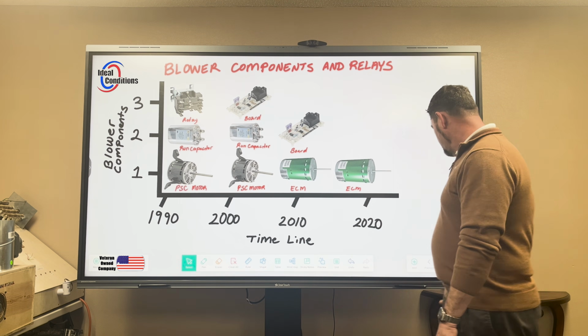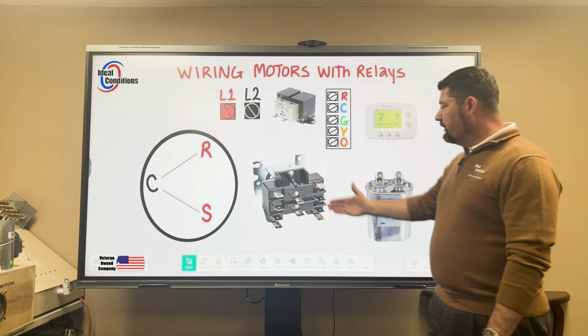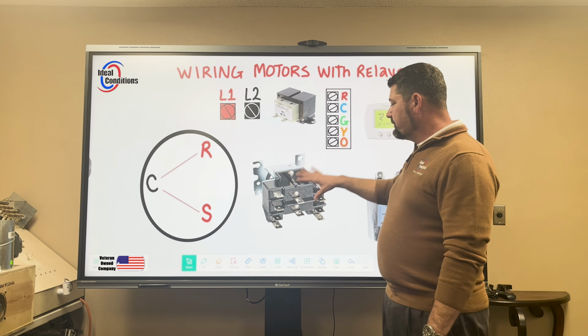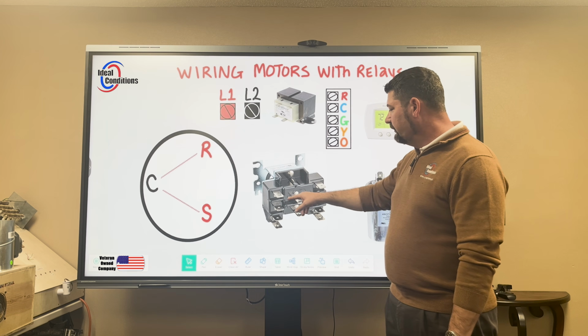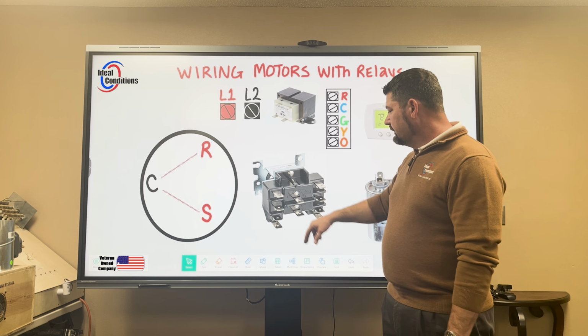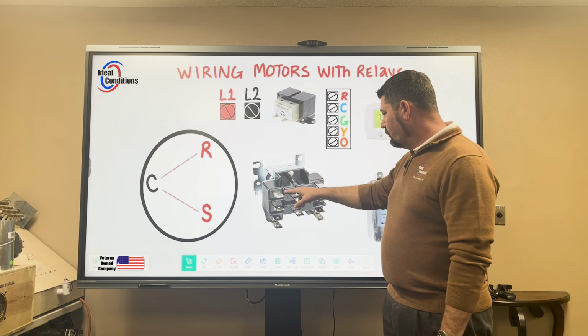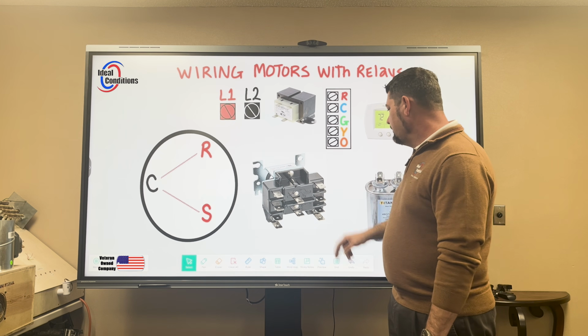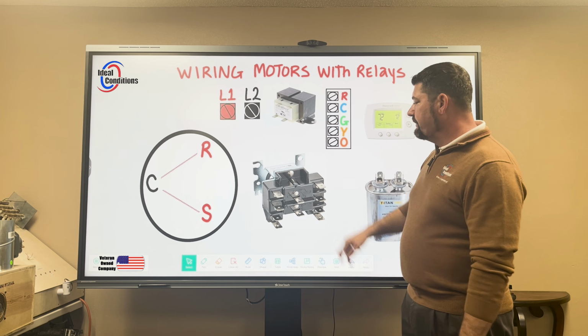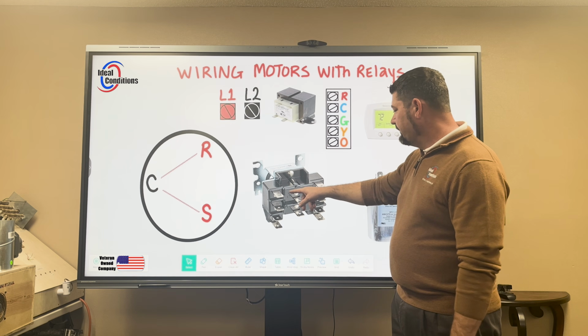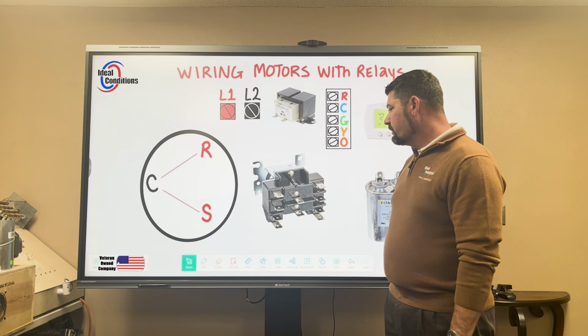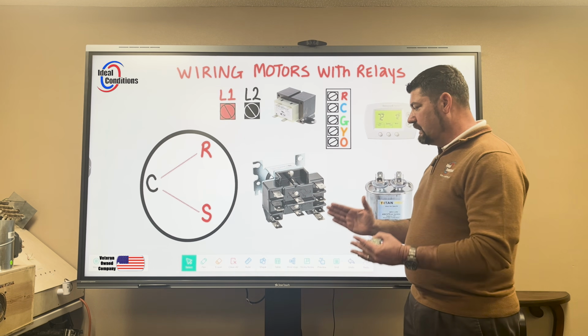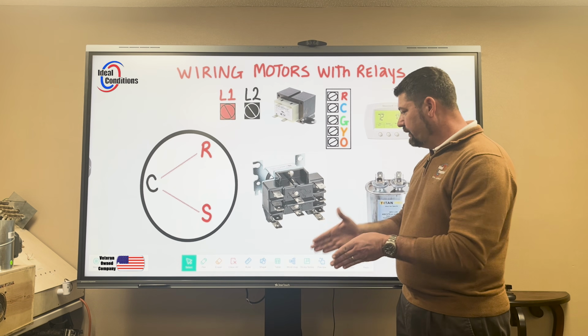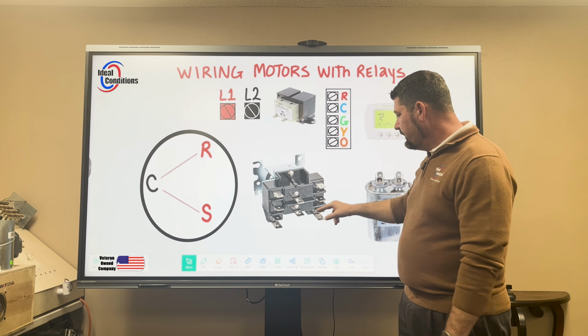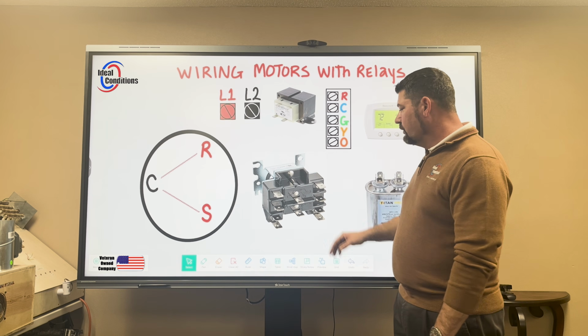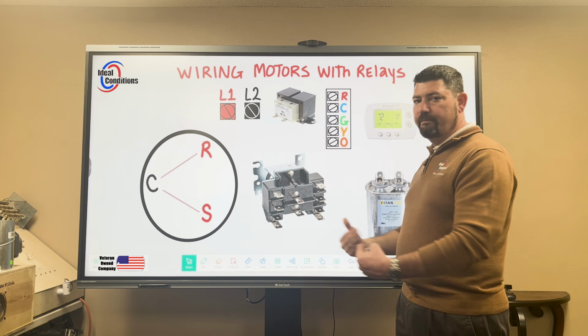Getting right into it, the 9340 relay, we have this image up here, blown up so you can see all these terminals. This is a good clear image. It talks about the different jobs it can do. Just by looking at this, terminals 1 and 4 are pretty much your line inputs, and then terminals 2, 3, 5, and 6 would be your load outputs.